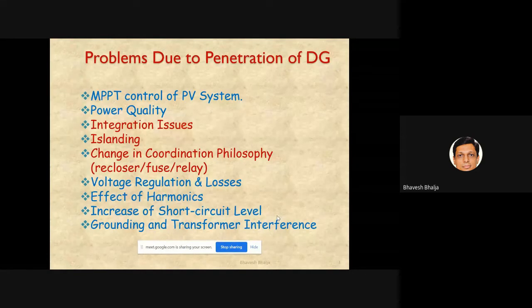Now if I connect distributed generators into the grid at different locations, let's say a total of 10 DGs, each of 5 megawatts, or 50 megawatts in total, obviously this is going to increase the short circuit level. And if the short circuit level increases, then I need to change the breaking capacity of the circuit breaker, because the existing circuit breaker is not capable of withstanding that much fault MVA. So the only option is to change the circuit breaker. A circuit breaker is a very costly device.